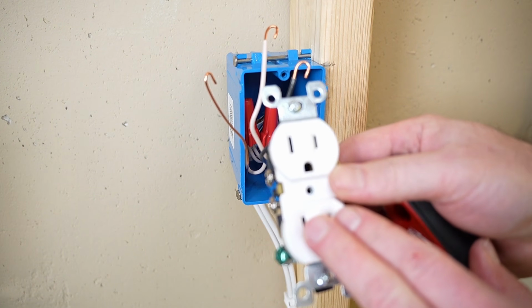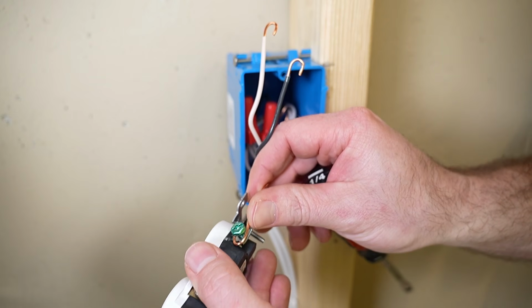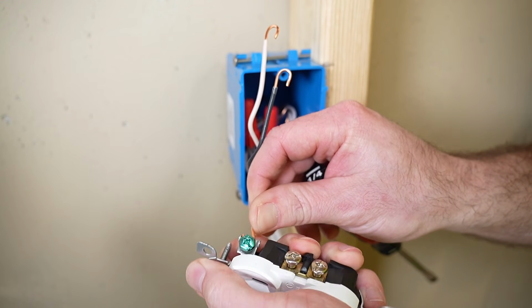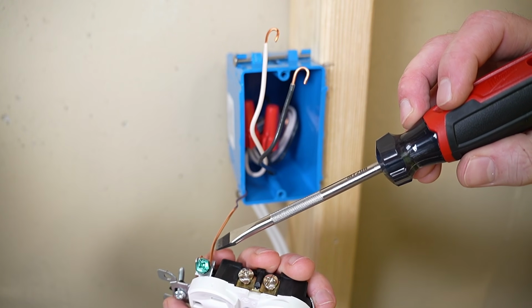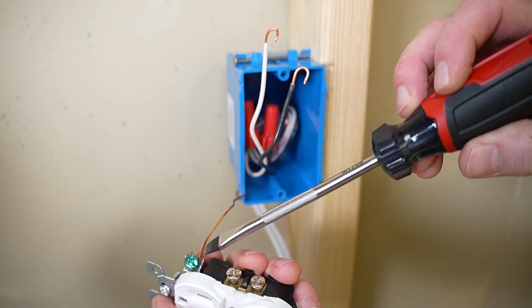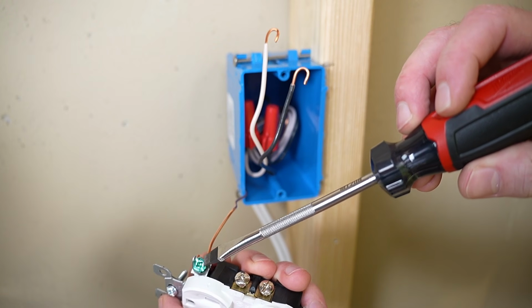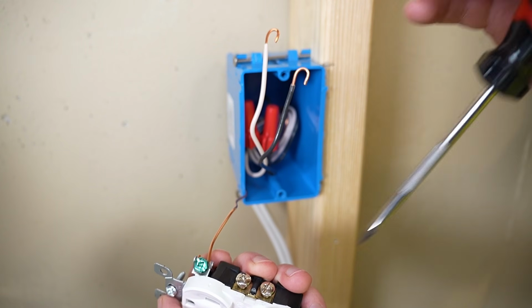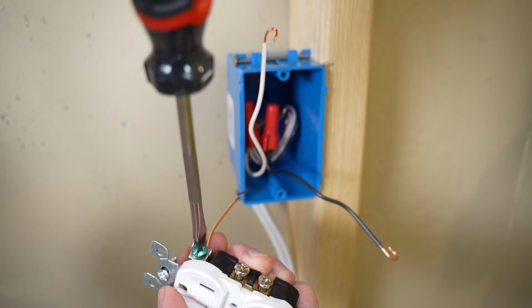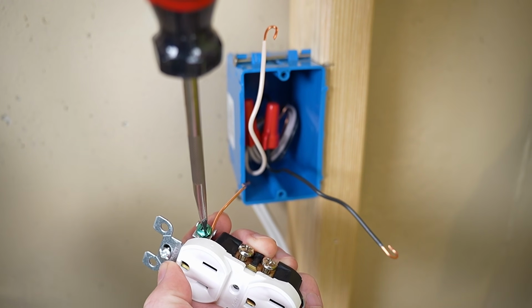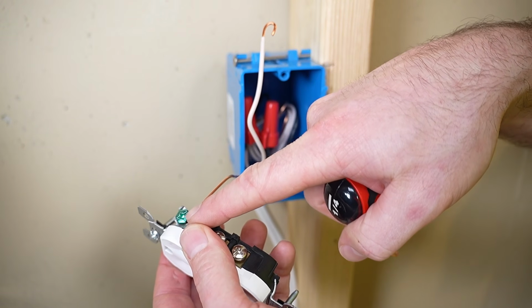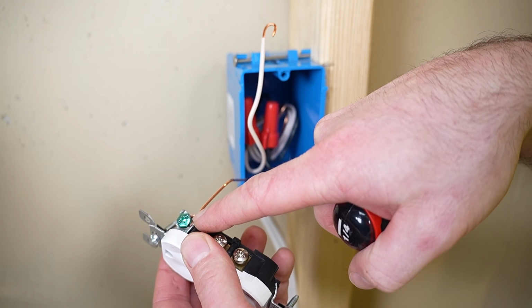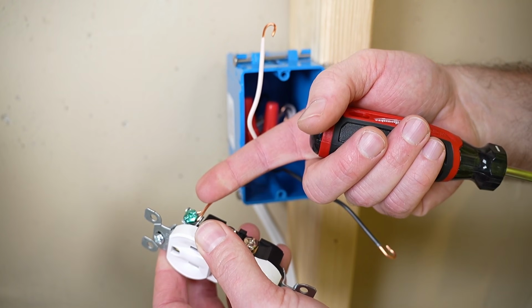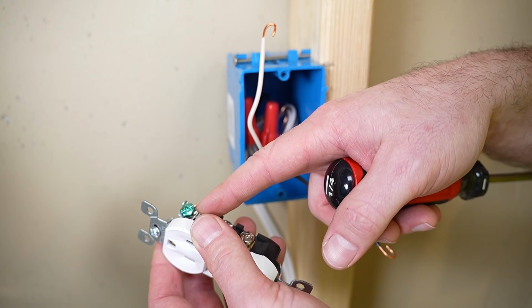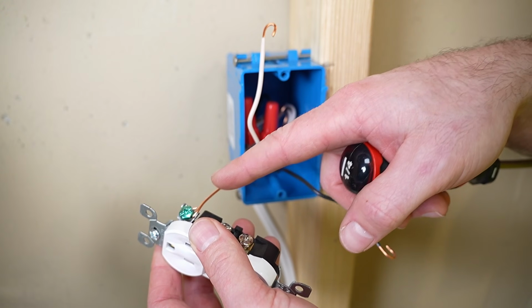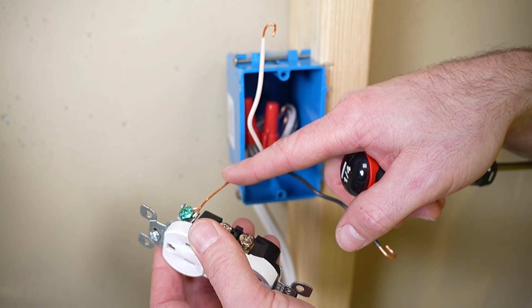And now we're ready to start installing these. So I'll grab my ground wire first and put that loop around the ground wire. We want to make sure that that loop gets installed on the terminal in the direction that the screw is going to turn when we tighten it down. So as we tighten this screw down, it's grabbing the wire, and it actually pulled a tiny bit more wire in as that screw gripped and spun around. If we were to have that loop in there the opposite way, it would actually push wire out. So we wanna make sure these loops are the direction that the screw is tightening.